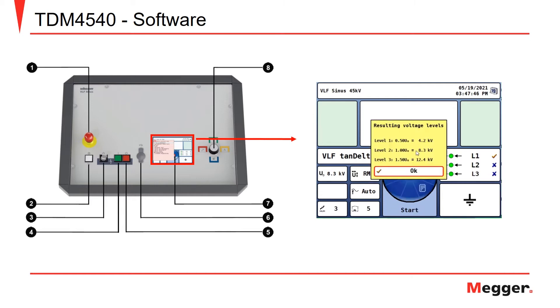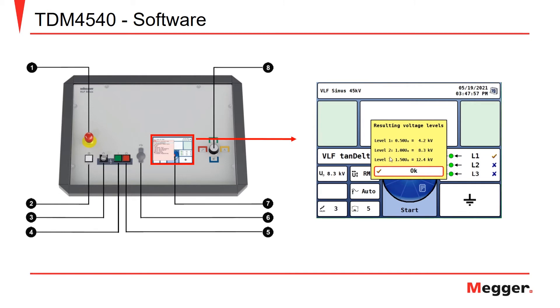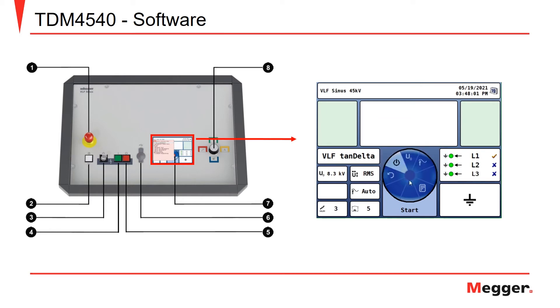Now you can see the steps, the resulting voltage levels of testing. Level one will be 0.5 U-naught, which is 4.2 kV. One is at 8.3 kV, and 1.5 U-naught is 12.4. Select OK.